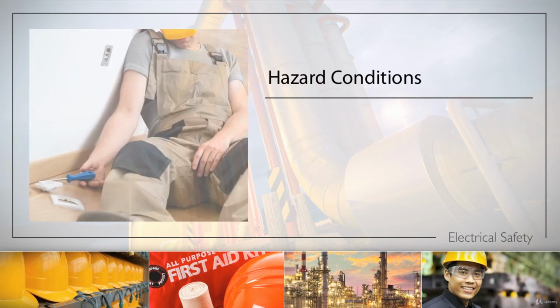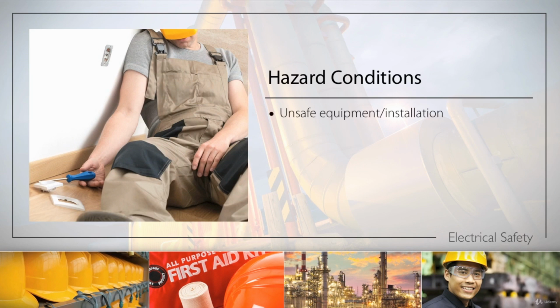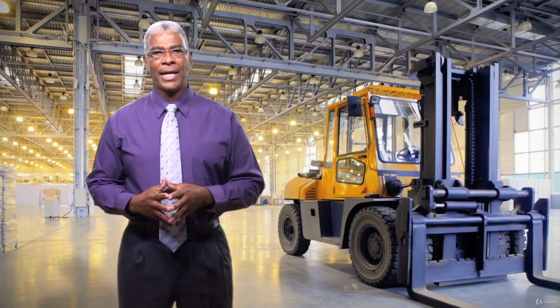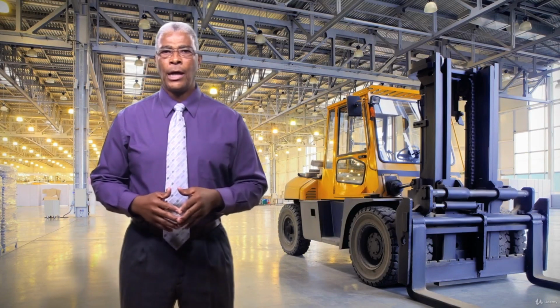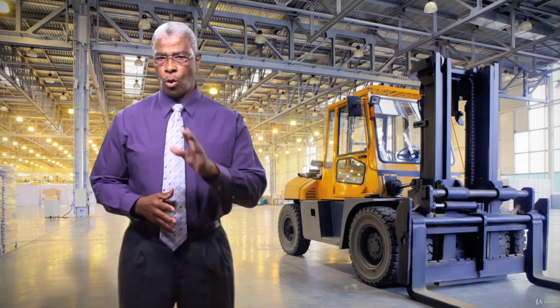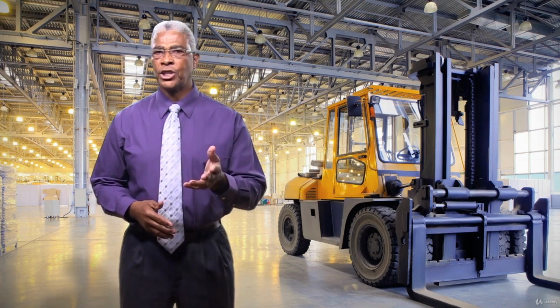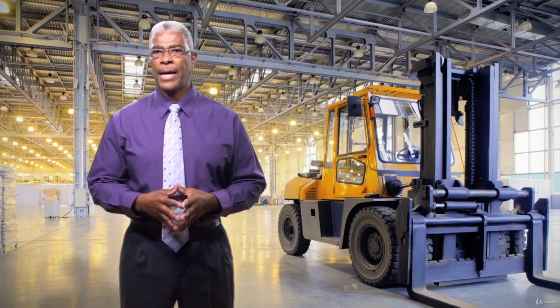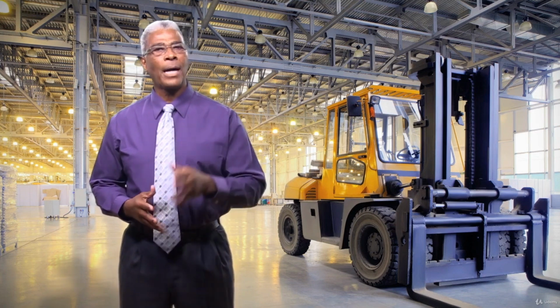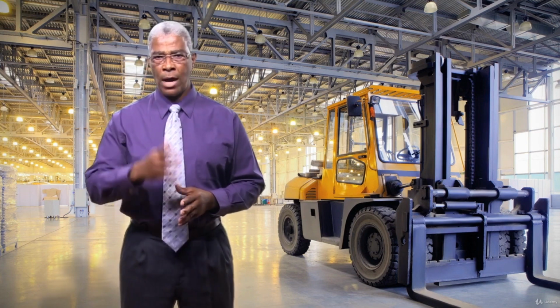Now, let's look at the conditions in which these hazards occur. Electrical accidents are caused by a combination of three factors: unsafe equipment and/or installation, an unsafe environment, and unsafe work practices. If you are at a work site, watch for clues that electrical hazards exist. These include tripped circuit breakers or blown fuses, warm tools, wires, cords, connections, or junction boxes, a circuit shut off by a ground fault circuit interrupter, which we'll talk about later, and worn or frayed insulation around wire or connection.